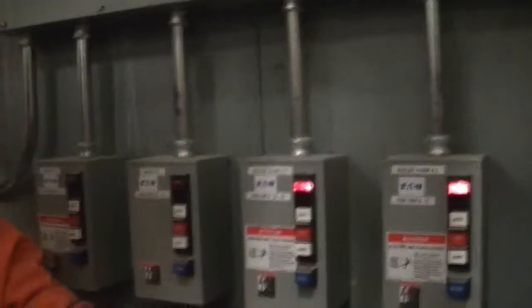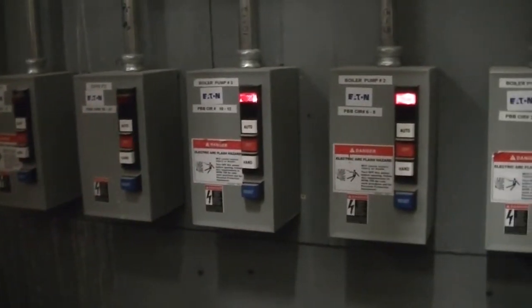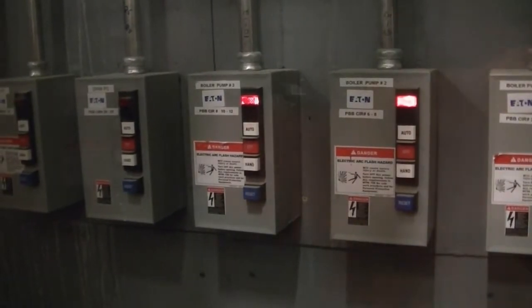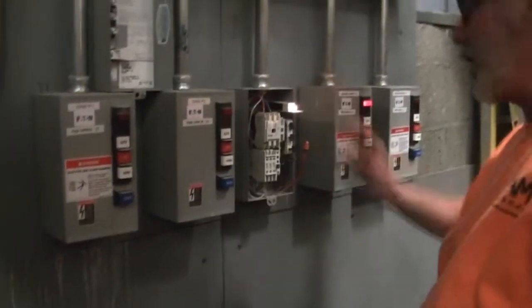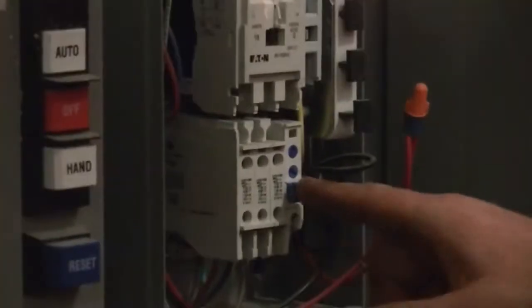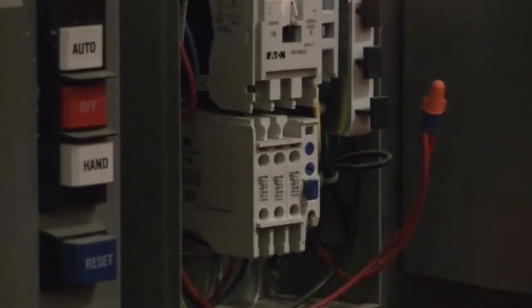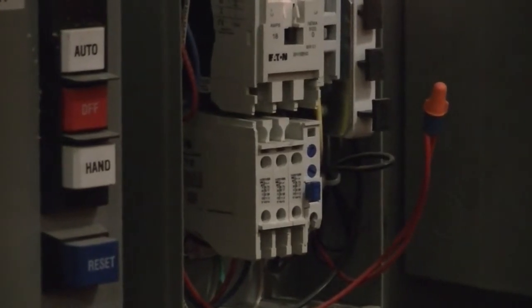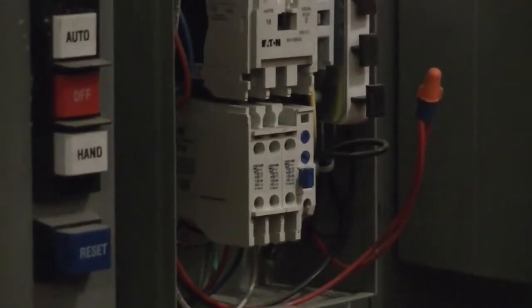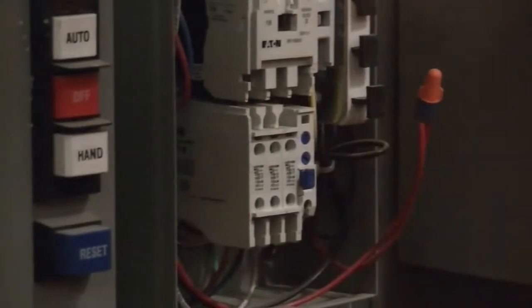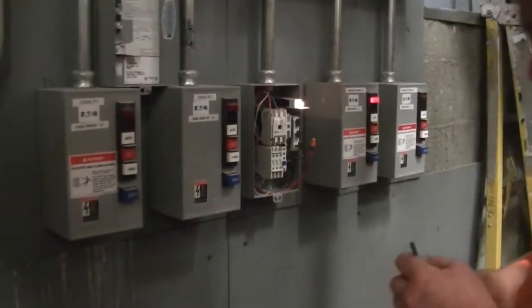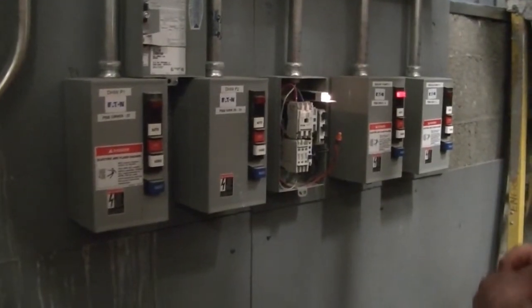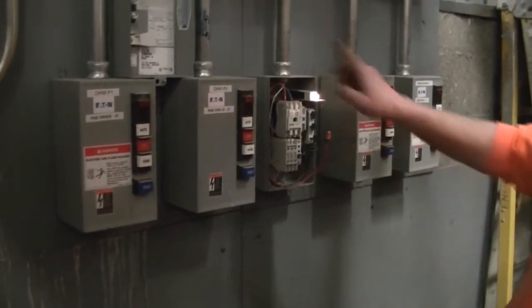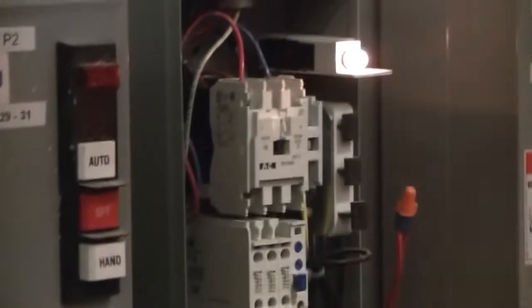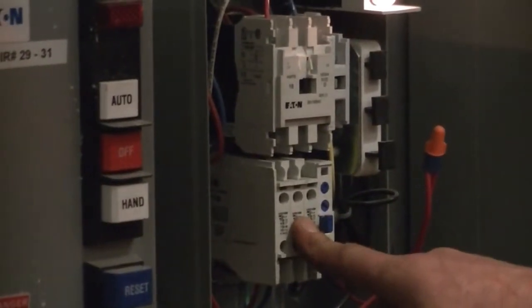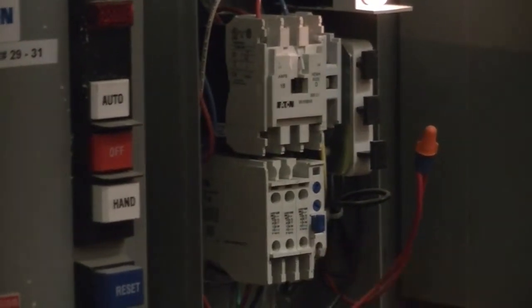If you can't reset, does anybody have a screwdriver on them? No? So inside each one of the pump starters, there's an overload, there's a reset plunger for the pump. These are single phase, but you'll see 3 heaters in them. All starters are 3 phase until you get to the starter switches, which are very small. So what happens is power comes in through 2 of the legs. One of the legs circles up through the other heater in order to complete the heater circuit, okay?